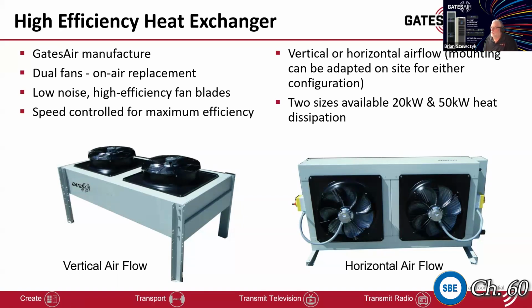The other thing is that these fans are specifically designed. They have a serrated edge, and I don't know if you've ever been near the chillers for a typical air conditioning system that doesn't have serrated edges. The fans tend to be a little more noisy. These fans are actually very quiet, and you can easily have a conversation next to the heat exchanger while they're running. That's important if your transmitter is located in a residential area, for example, with some neighbors within a few hundred feet of where these are going to be mounted. They probably don't want to hear a lot of fan noise.